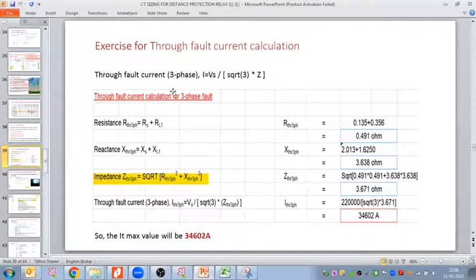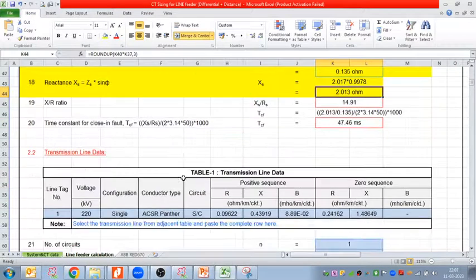So now the through fault current calculation for the three-phase fault. The formula we follow is I equals Vs divided by root 3 into Z, so Z we need to find out. We already know the voltage is 220 kV, and I we want to calculate. For the three-phase resistance, RS plus RL, so 0.135 plus 0.356, giving 0.491. Let me go to the Excel now.